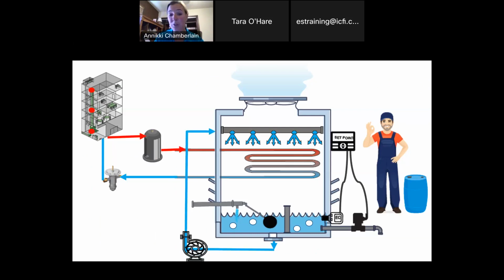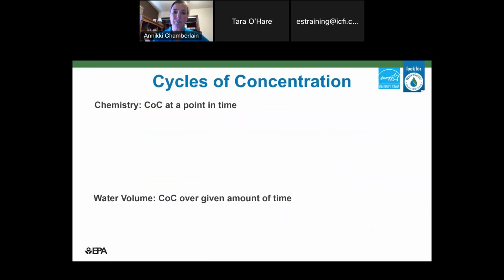Here we introduce, instead of the water that we're cooling going back into the system, we're basically recirculating it. So we introduce another recirculation pump. I've seen these fail, and basically there's a little sensor that once it fails, it just opens up the water flow, floods the machine, and it even sounds like it's running. The technician went and looked, he's like, no, it's running good, but they were having a 30,000 gallon a day failure. So tons of stuff that can happen. So I had briefly mentioned cycles of concentration.